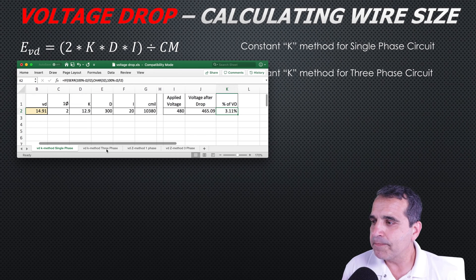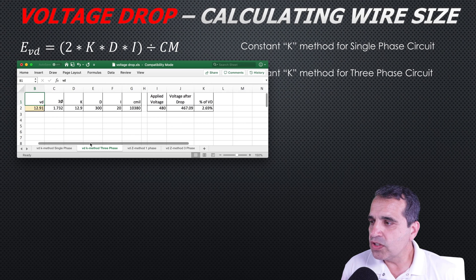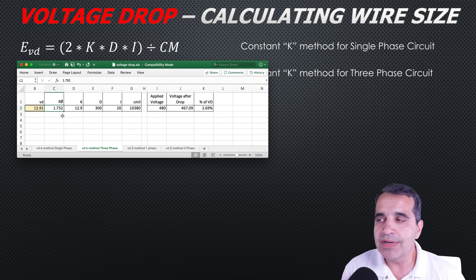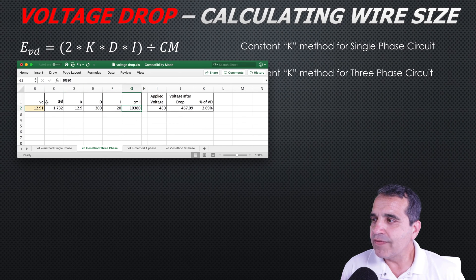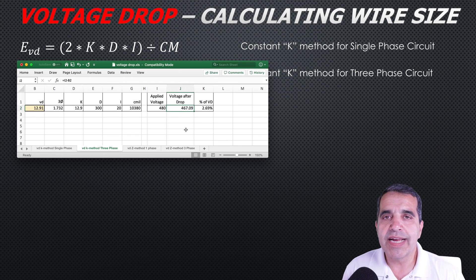Now let's look at the same scenario as a three-phase load. Using the square root of three (1.732) instead of two, with the same K value for copper, 300 feet, 20-amp load, and number 10 wire with its circular mils, we get 12.91 volts of voltage drop. On a 480-volt circuit that leaves approximately 467 volts at the motor — a 2.69 percent voltage drop, which is acceptable per the NEC informational note.